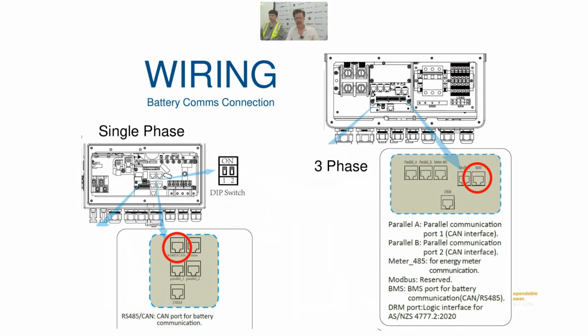In terms of the comms wiring for single phase and 3-phase, there's just parallel connections which are going to run between the inverters when you're connecting more than one. And as you can see here, there's the BMS port, and you've got the parallel ports. Each model is slightly different, so you'll need to check the manuals for that. But that's the only thing you're going to need to use these RJ45 ports for when you're wiring all up, unless you're in Queensland and you're using DRM, in which case you'll know about that.